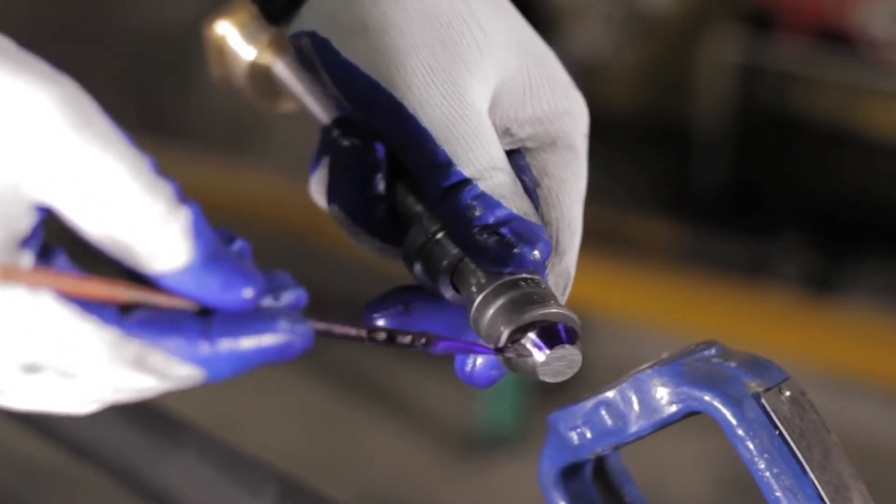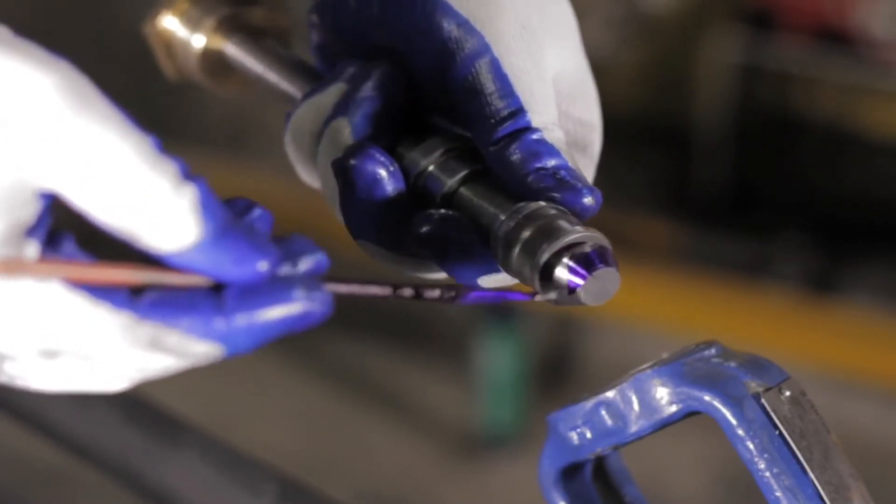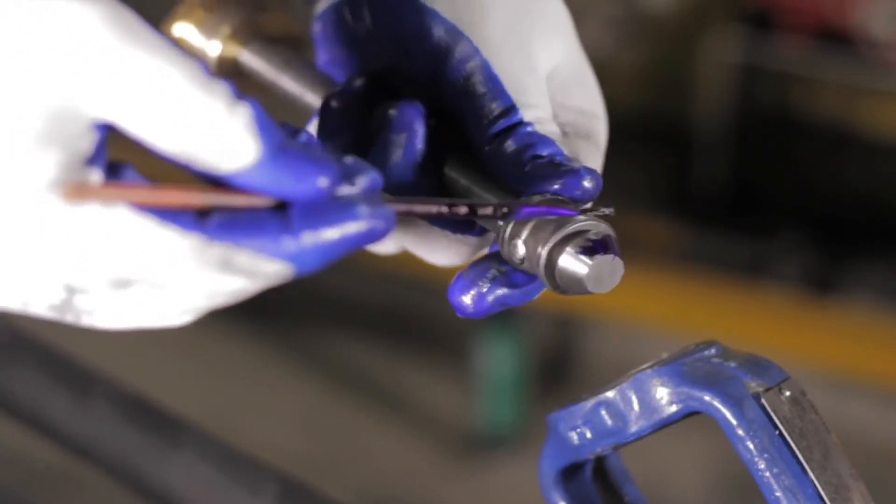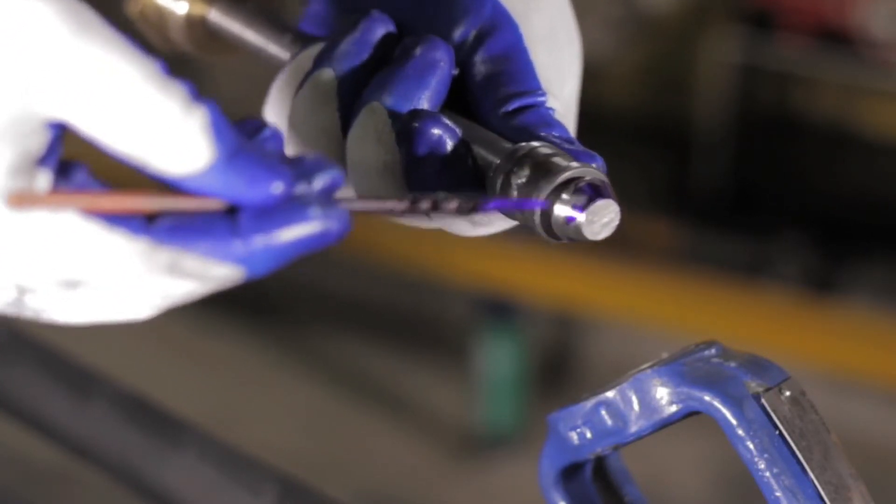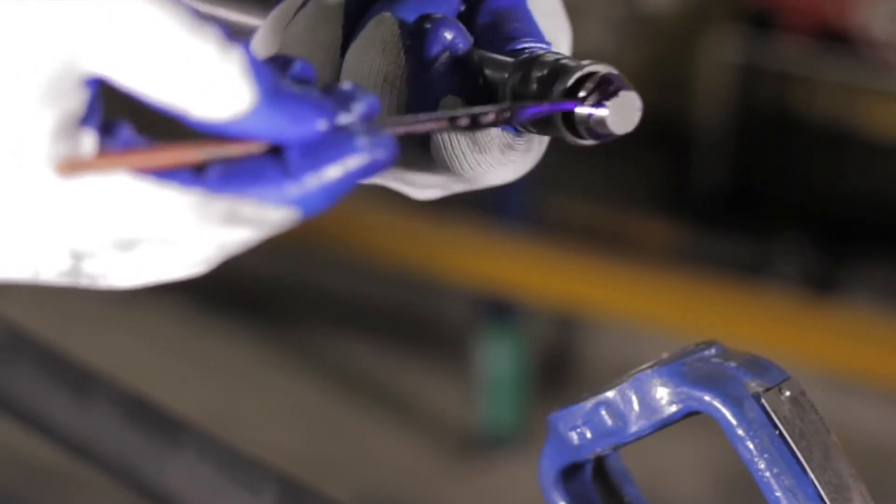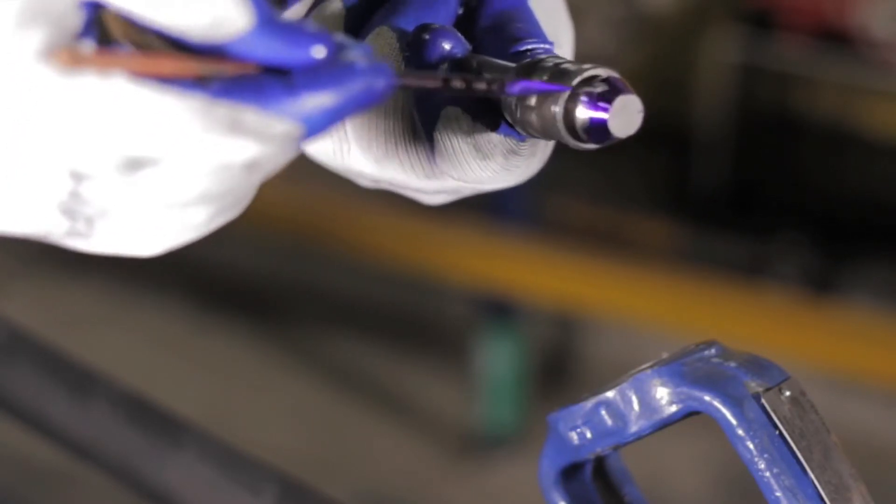A bit of bluing compound on the face of the new disc and seat assembly will allow you to check for a good disc to seat engagement. This is especially recommended for smaller valves or where visual inspection is difficult.